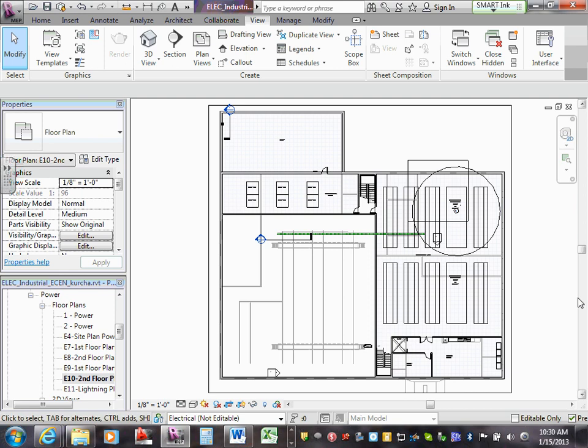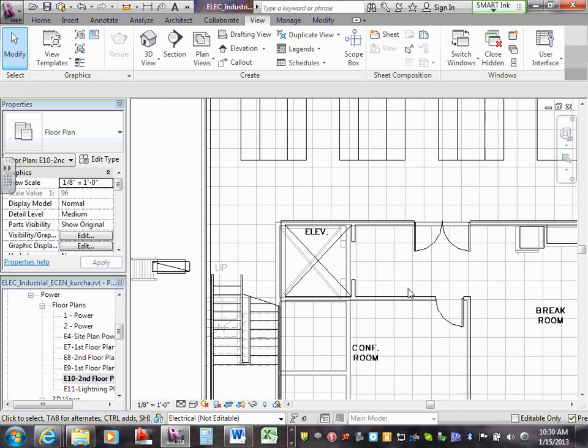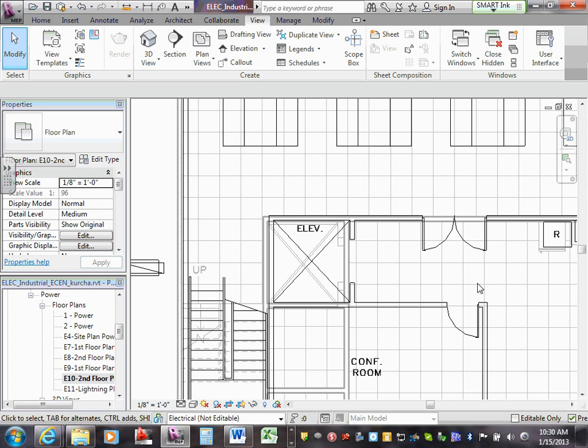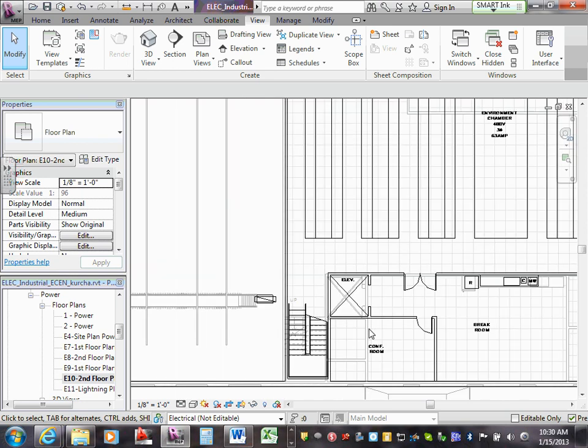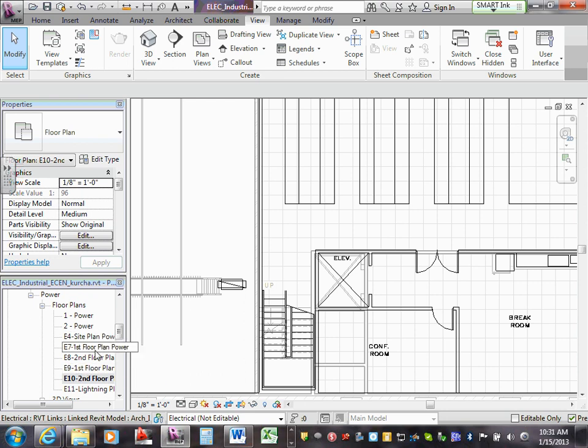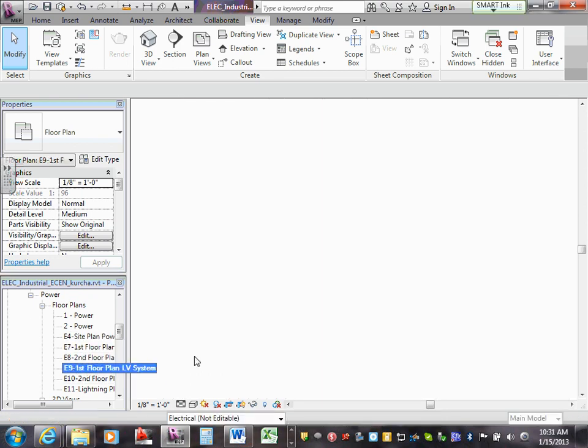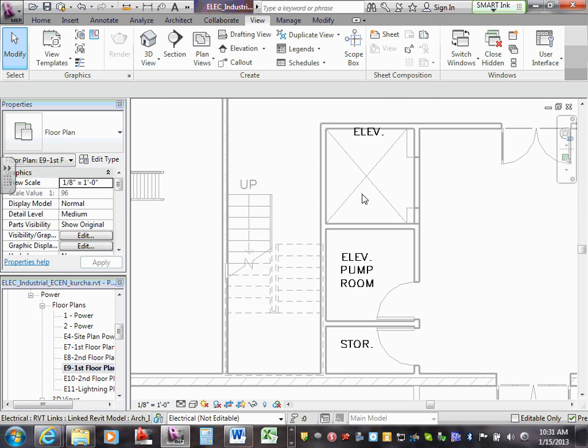Okay, that was the duct smoke detectors. That's required. The other thing that's required for this building is over here on the elevator. You're going to have elevator recall. With each elevator, there are going to be 4 control modules: primary, secondary, shunt trip, and firefighter's hat that you have to control. And that's usually going to be in the elevator machine room on the first floor. This is where you're going to have your 4 control modules.